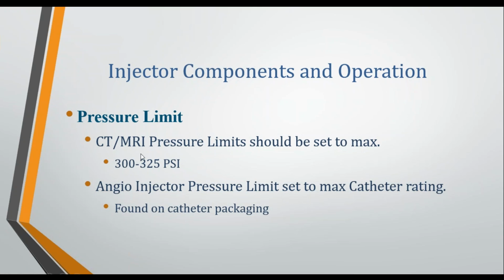But the difference between the angio injector and the CT injector is that all CT and MRI injectors go through an IV needle. All CT and MRI injections are performed through an IV needle. So it's basically the same size orifice that every single shot is being shot through. Angiographic injections, on the other hand, are injected through catheters. All angiographic procedures don't shoot through IV needles, they shoot through catheters. And there are multiple size catheters, different lengths and diameters of catheters. So the pressure limit for angiographic procedures is determined by the rating of the catheter. If you look on the packaging that the catheter came in, one of the items listed on there is the pressure rating of the catheter. That's what the pressure limit should be set to for angiographic procedures. Catheters range anywhere from 600 psi to in excess of 1200 psi in some cases.